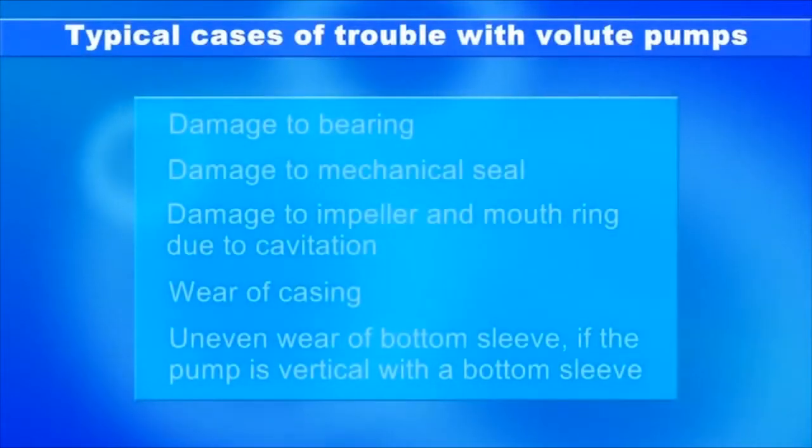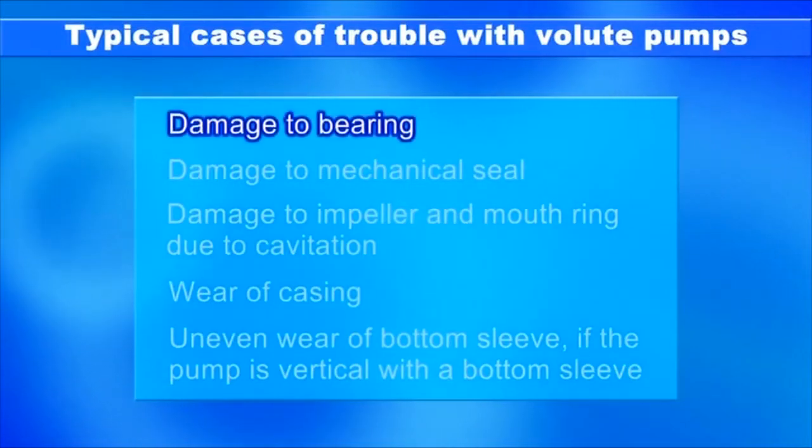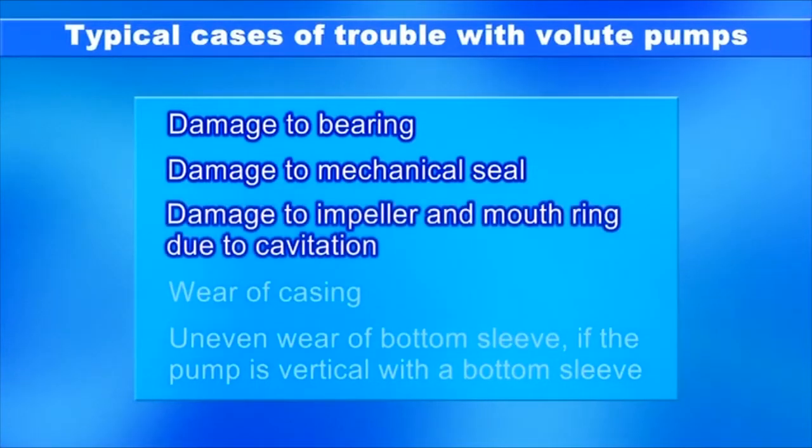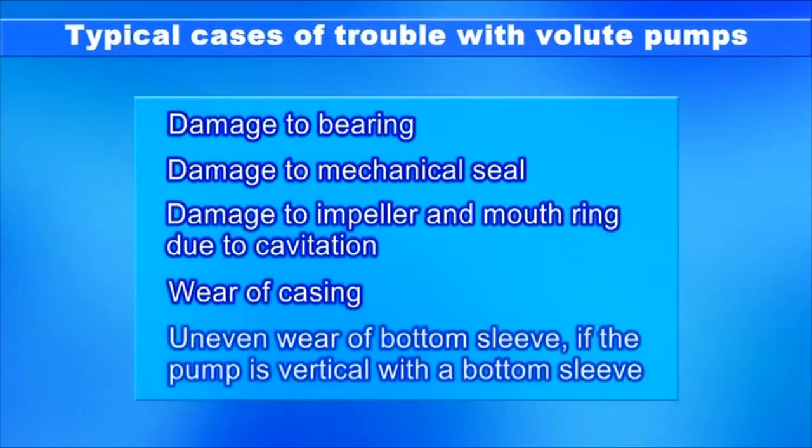The following volute pump cases of trouble have been reported: damage to the bearing, damage to the mechanical seal, damage to the impeller and mouth ring due to cavitation, wear of the casing, and uneven wear of the bottom sleeve if the pump is vertical with a bottom sleeve.